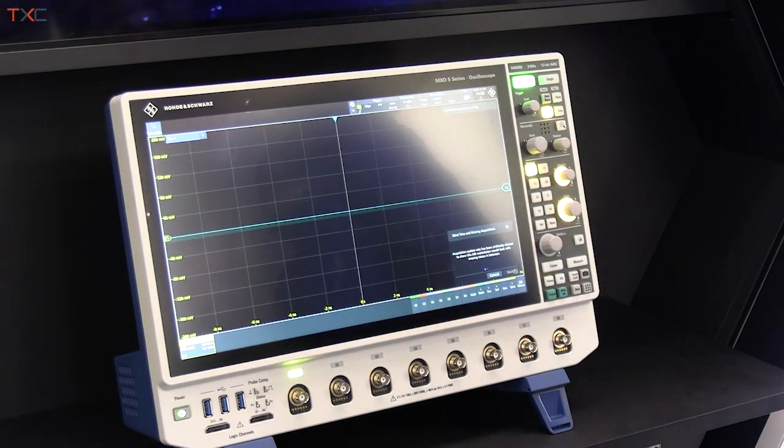Let's use all 8 channels with the demo functionality here. Let's jump into the menu, then demos, and then power. Here we can use the power sequence on all channels. The instrument will tell us to disconnect all cables and probes — as you can see, nothing is connected. Now the instrument activates all 8 channels.